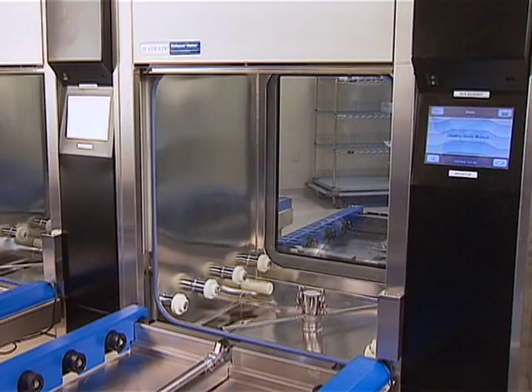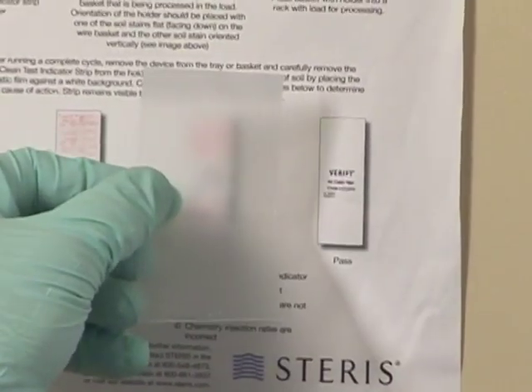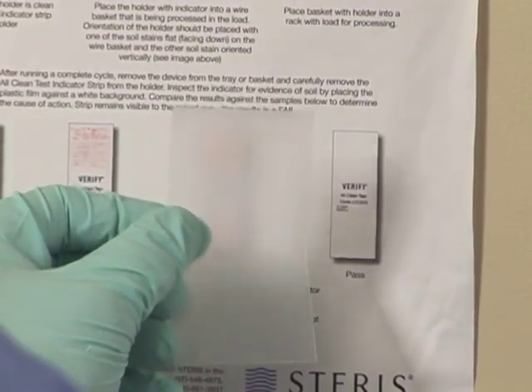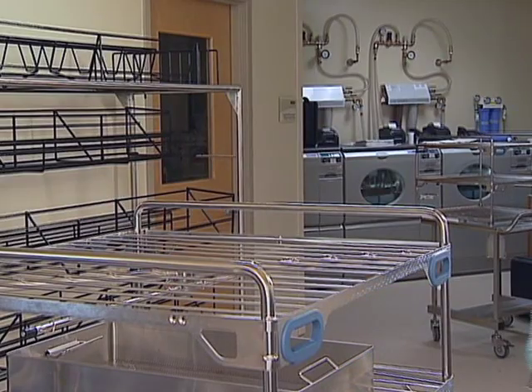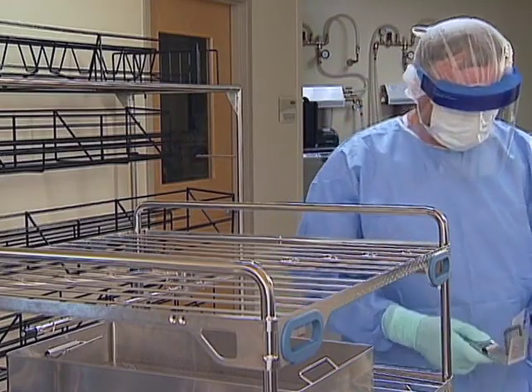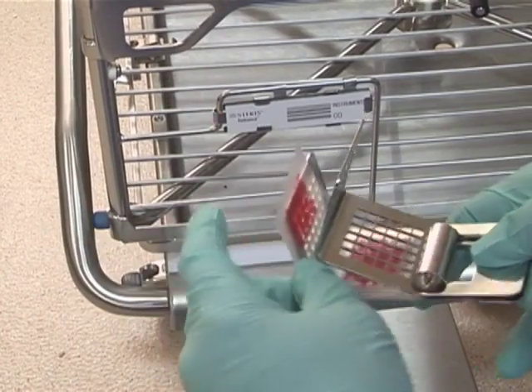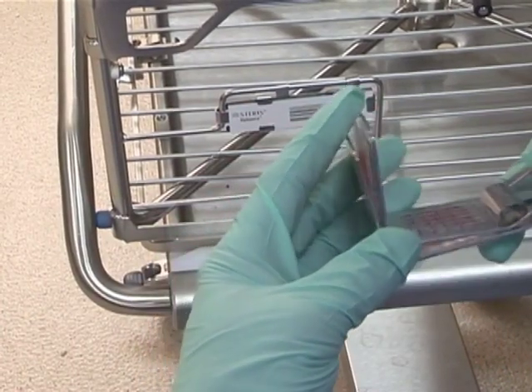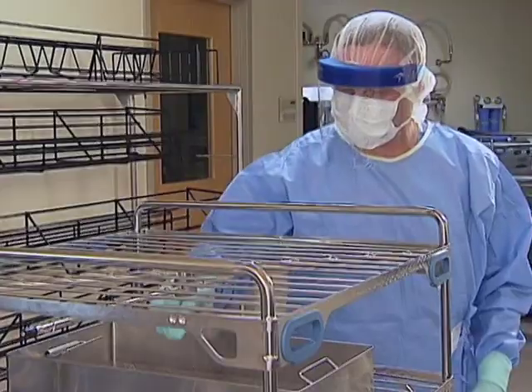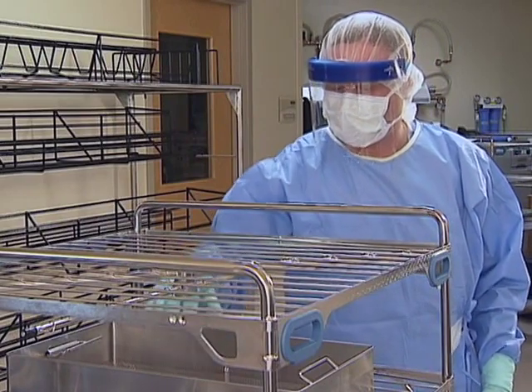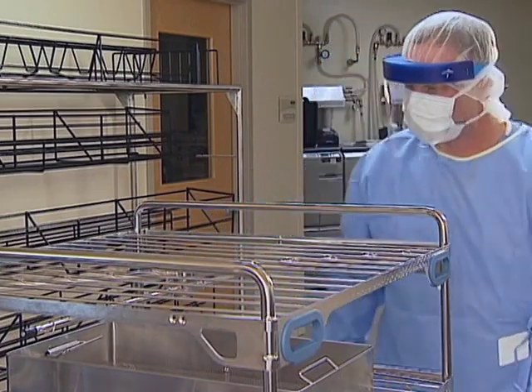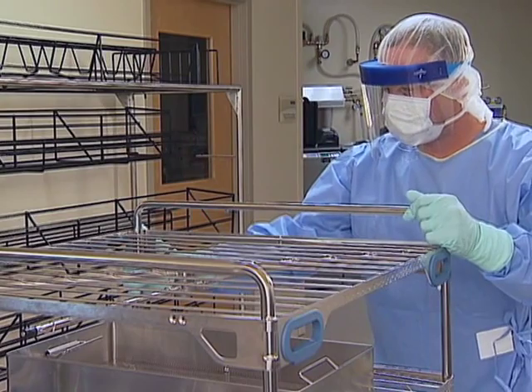To effectively monitor the parameters of your Vision Single Chamber Washer, STERIS recommends using the Verify All Clean Test Washer Indicator on a daily basis. Professional standards organizations recognize the importance of monitoring your mechanical and chemical cleaning process. The Verify All Clean Test Indicator ensures the essential parameters, time, temperature, chemistry, and impingement have been appropriately achieved.